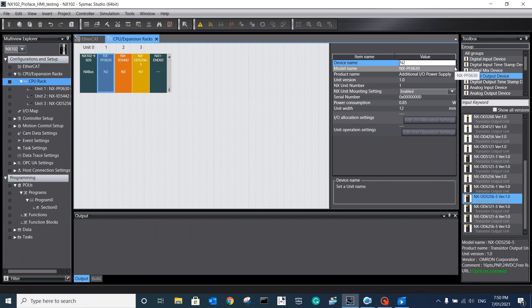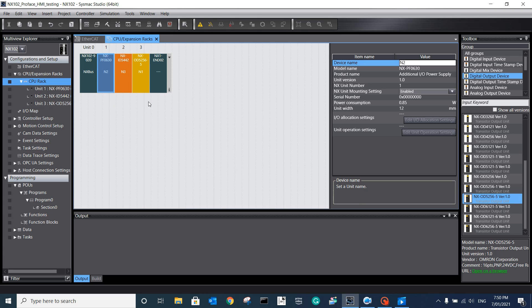Hi guys. In this training tutorial, I'd like to show you how to set up Omron's NX102 PLC to talk to the Proface HMI. I just created a project using the NX102 PLC, and configured some digital input-output modules in the local connection. For this NX102 PLC, if you want to use the local connection, it is necessary to add one of these power supply modules to supply the local 24V DC for the I/O DC bus.